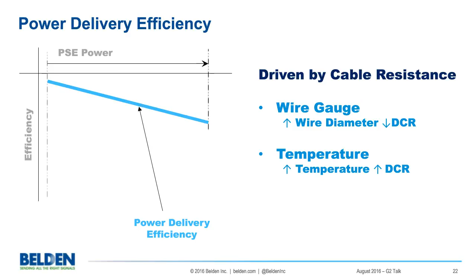So what does this mean? Well, if we look at the different gauges of cabling generally available in data cabling, we can see that it's more efficient to use larger diameter conductors. The graph on the top is cabling using 22 gauge wire. The second one is using 23 gauge wire. The third one down is 24 gauge wire, and lastly the one on the bottom is using 26 gauge wire. As you can see, as the power goes up, the PSE is the power supplying equipment. As more power is expected to go through the cable, the current goes up, and that causes more power loss through the cable, and that's where the efficiency comes through. So if we keep the DC resistance down, we're going to be more efficient.